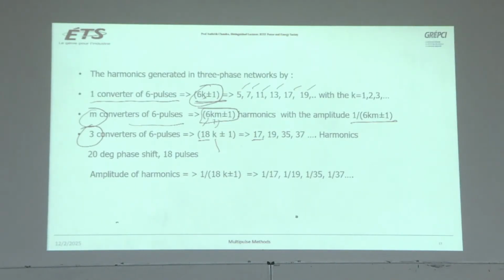3 6-pulse converters means 18 pulses. In 18 pulses, the minimum you will have is the 17th, 19th, and then the 35th and 37th. See, this is a big advantage. If you are using 3 6-pulse converters, you are having 18 pulses, but you will have 60 divided by 3, a 20-degree phase shift. So between the 3 converters, you should have a 20-degree phase shift to get this advantage, so that many harmonics of this amplitude are removed.